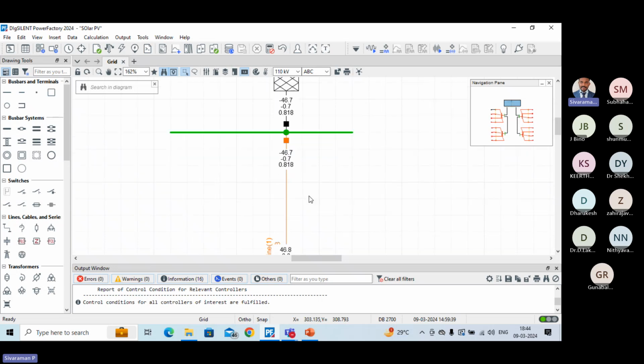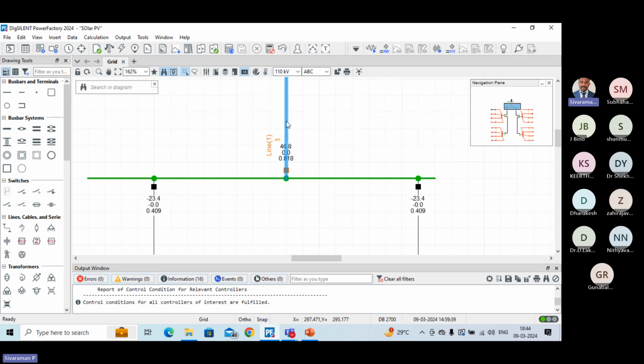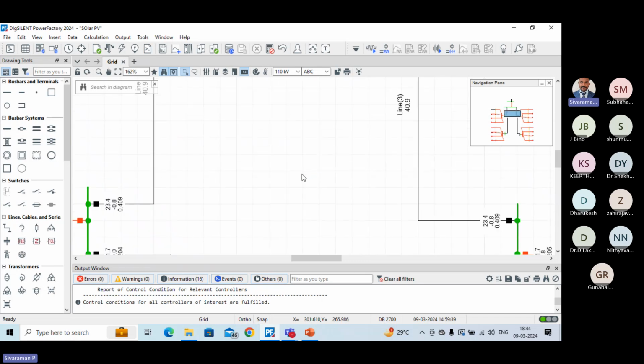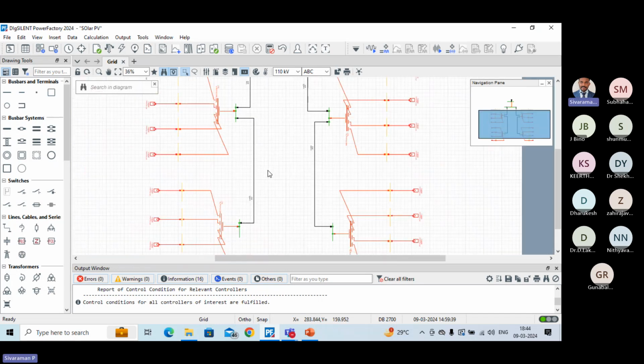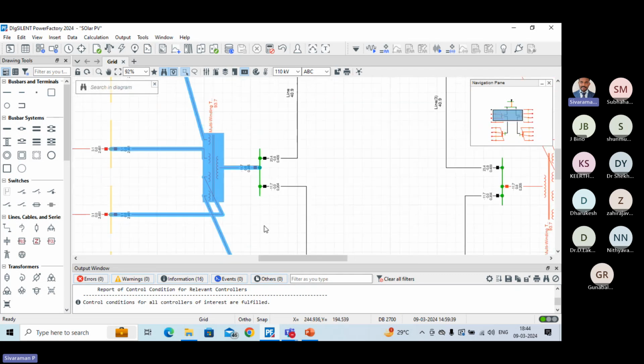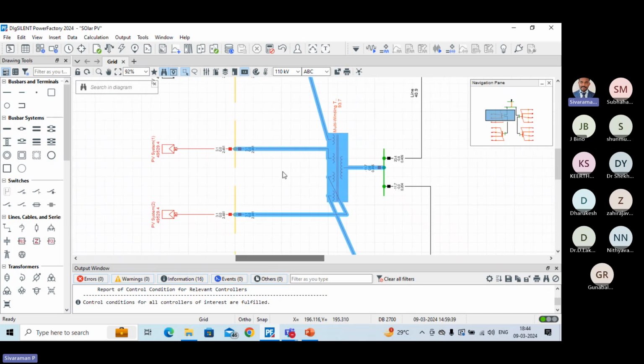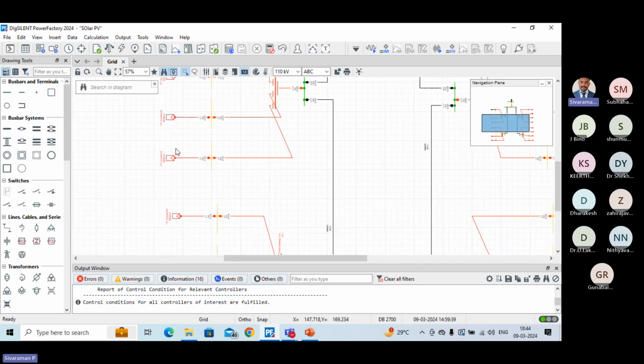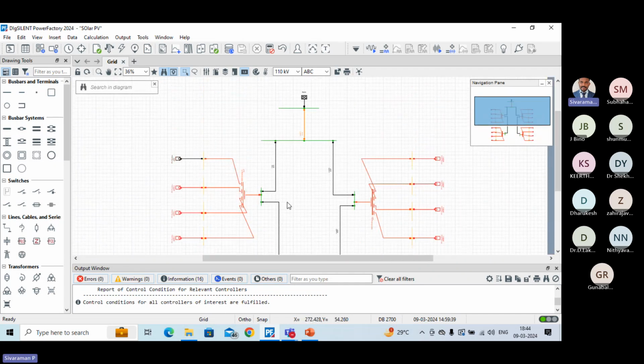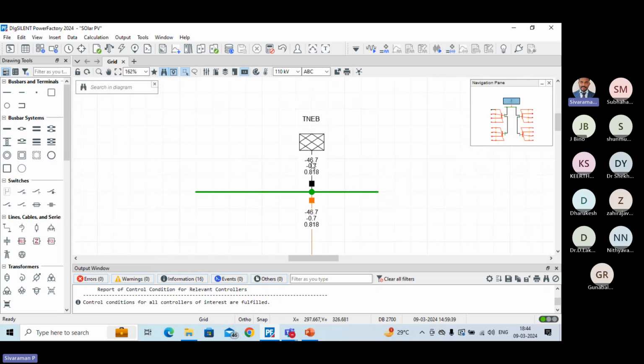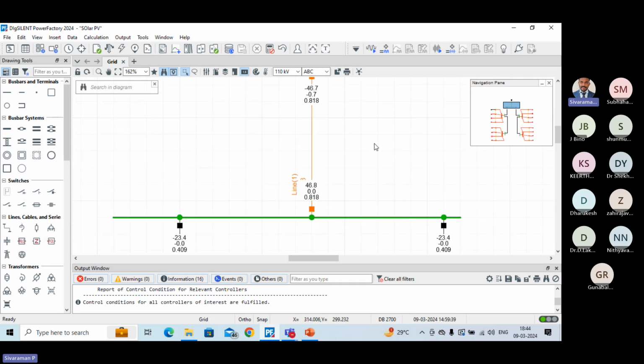That is the losses in the system. So losses in this medium voltage cable, that is the collector network cable, then losses in this inverter duty transformer, then losses in these DC cables. These are all the things we have to consider. So now it is no longer 50 megawatt. Presently it is only 46.7 megawatt.